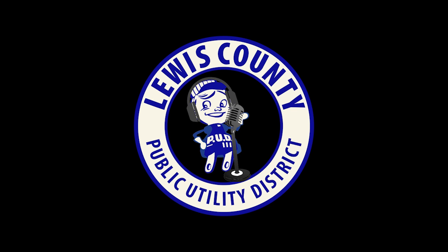Again, if you have to get out, the hop and shuffle method is widely advertised. That's due to when there's a fault or a line on the ground, it's essentially pumping a lot of energy into the ground, and the ground itself can have a voltage, called a voltage gradient, so it can change the voltage on the ground. You're not at zero volts anymore. But even if you're not at zero volts, you want to be at the same voltage, you don't want a difference in voltage, because that's when current will flow. By taking a step where there's a voltage gradient on the ground, you could have a voltage difference between each of your feet.